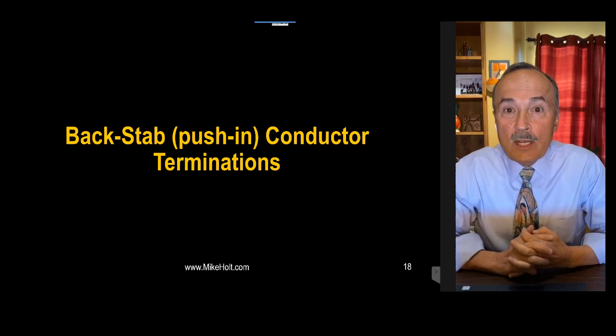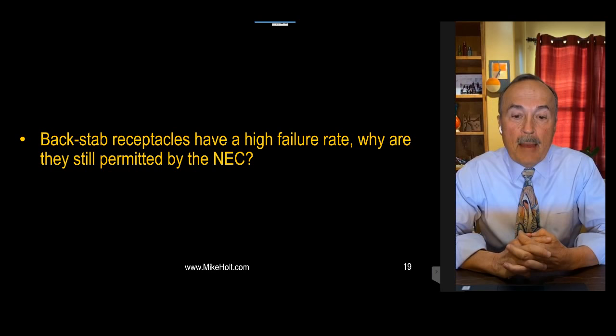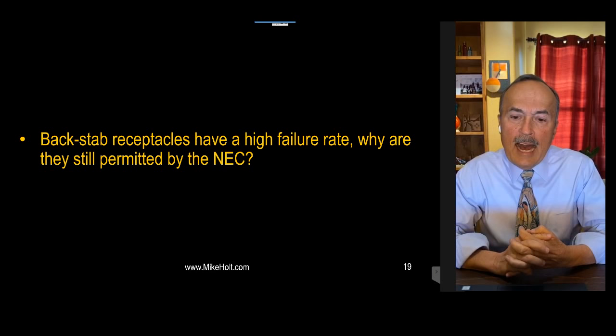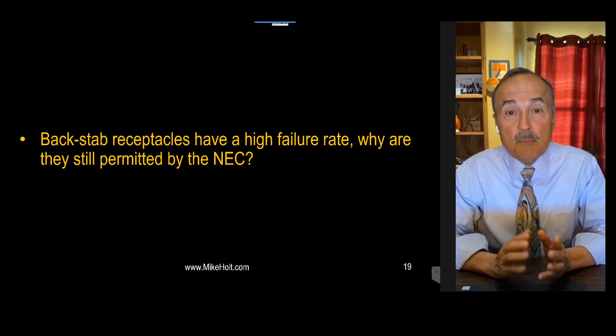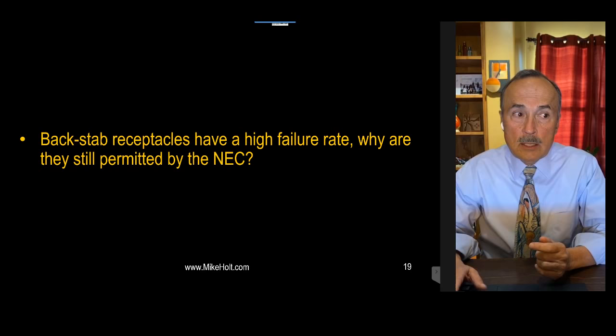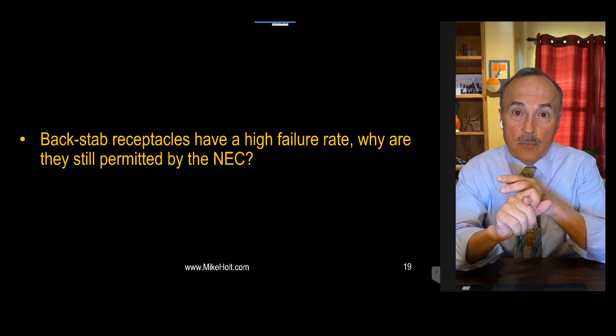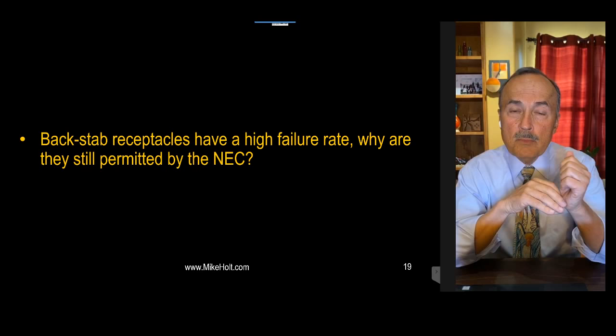The first question is about backstab, or push-in conductor connections. The question is: backstab receptacles have a high failure rate — why are they still permitted by the NEC? I don't know that they have a high failure rate. Maybe those doing service work would say I haven't been in the field long enough to know. They're a listed product, listed for a solid 14-gauge conductor. Years ago they were permitted with 12-gauge solid, and there were problems. So it's 14-gauge wire.